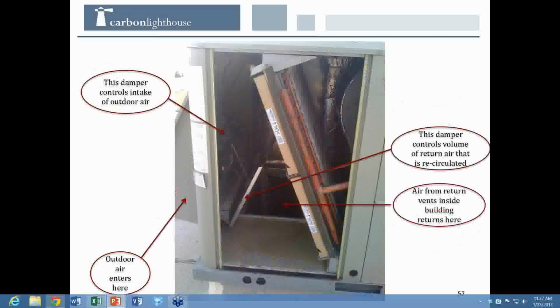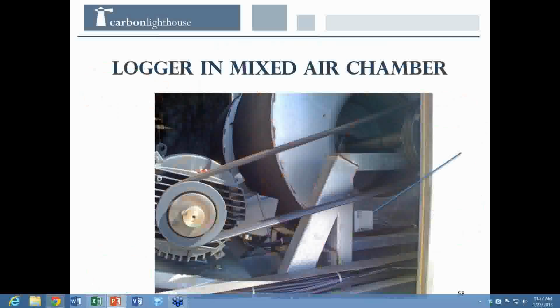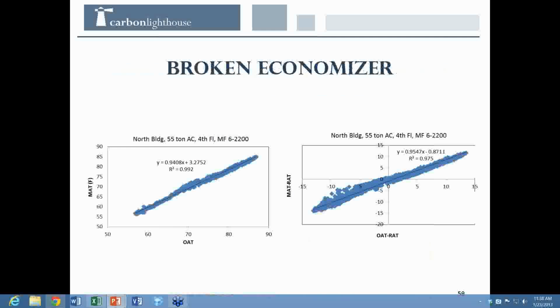So how do you figure this out? Well, you use data loggers. The blue arrow there is pointing to one of these little data loggers. This is just before the supply fan, so what we're measuring here is the mixed air temperature, the temperature of the air after return air and outside air have been mixed but before it's conditioned. If you look at the mixed air temperature and compare it to outside air temperature, what you should see is not this.